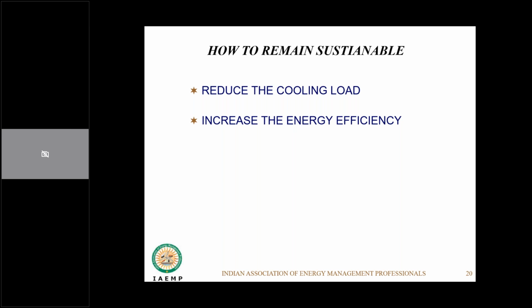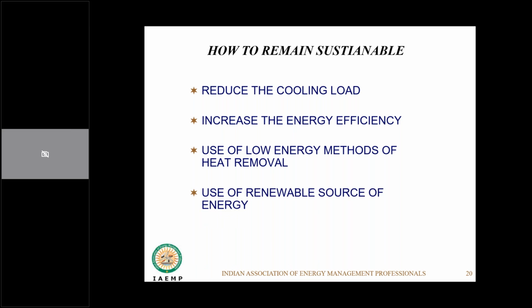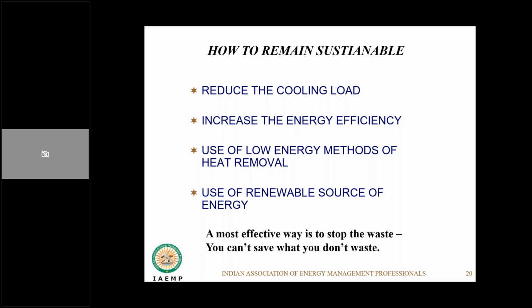Once you have found out what the sources of energy coming in are, we need to look into how we can reduce it. Improve the energy efficiency, so we select equipment which is highly efficient. Look at the avenues of low energy heat removal. So we sometimes need to break up the heat loads into different avenues and see how we can use different strategies for removing different heat loads. And use renewable energy as a source for heat transfer, so that we don't use costly electrical energy for this.